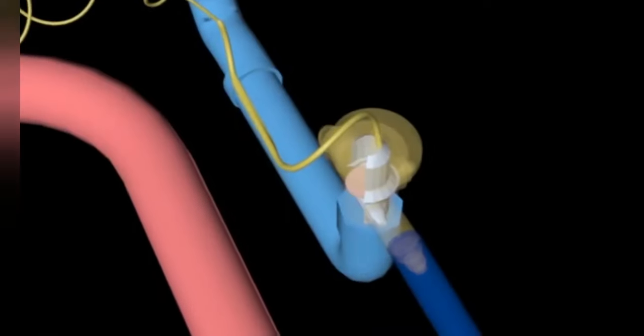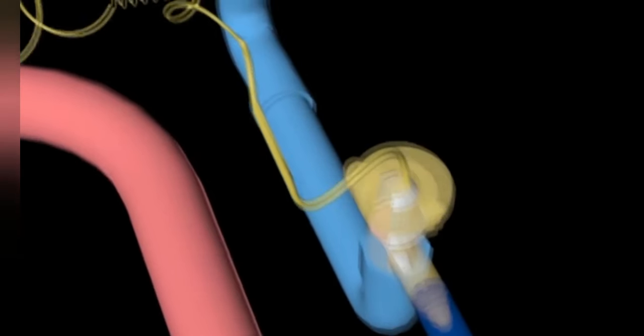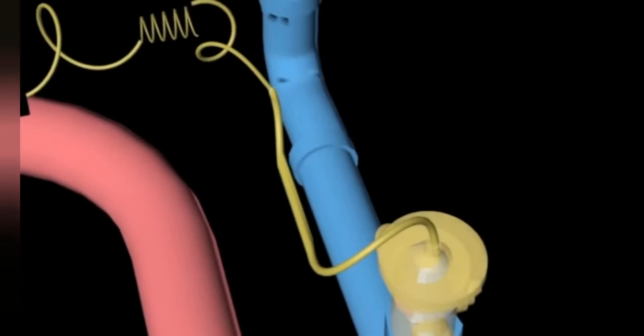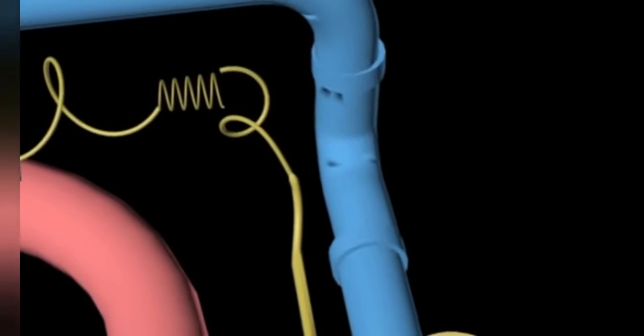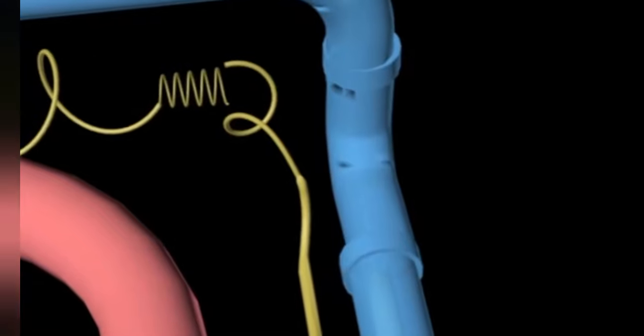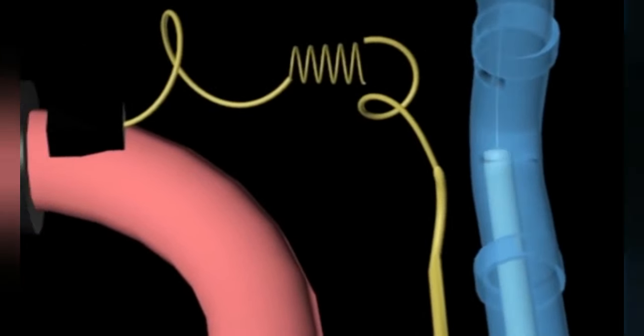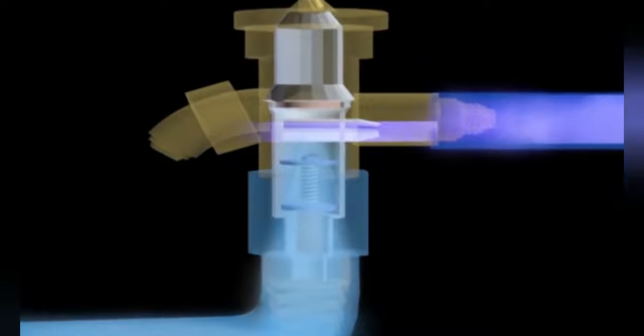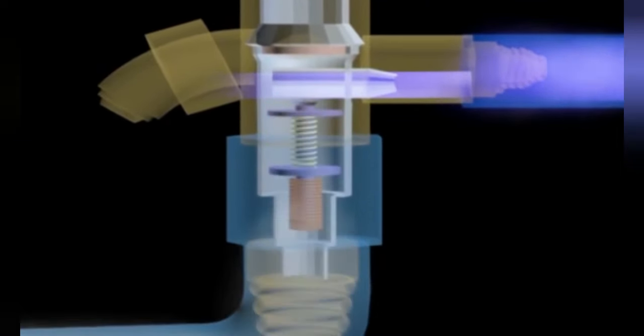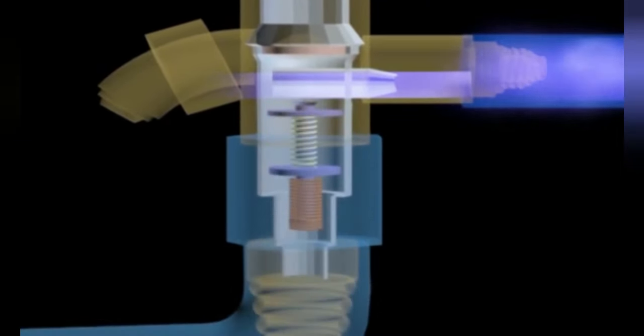A sensing bulb placed on the outflow of the evaporator detects the temperature of the refrigerant and sends a signal to the TXV. The needle valve in the TXV then controls the flow of refrigerant based on the transmitted signal.